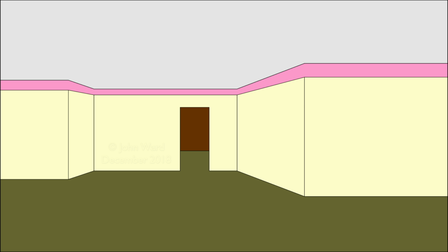So first of all then is the zone 150mm from the ceiling, and we can see that highlighted in pink here. So this effectively goes around the entire room, and provided your cables are within 150mm of the ceiling, that's about 6 inches, then you can put any cables in there that you want. So quite a handy thing if you say got concrete ceilings or something, you can put all the cables around there in that particular zone, and they can then be plastered in later. Or another thing you can do is put coving up there, and then you can actually put the cables, say, behind the coving. Wouldn't even need to necessarily recess those in the wall. The coving, of course, has a space behind normally when it's installed. So any part of that, basically just down from the ceiling, perfectly fine to put all of your cables in there.